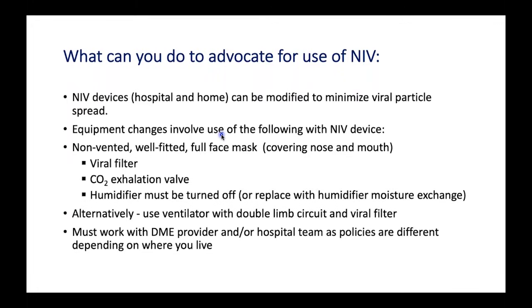You have to add a viral filter, a high quality viral filter. Those HEPA filters in your devices are considered viral filters. You have to have a CO2 exhalation valve. Since you just took away the mask, those little holes in your mask that are exhaling CO2, you have to add an extra valve somewhere in the system. And then your humidifier that's attached to your device or integrated into your device needs to be turned off, because otherwise the humidifier can make the filter wet, and once it's wet, it's basically unusable. Okay, so that's how you can modify your device.